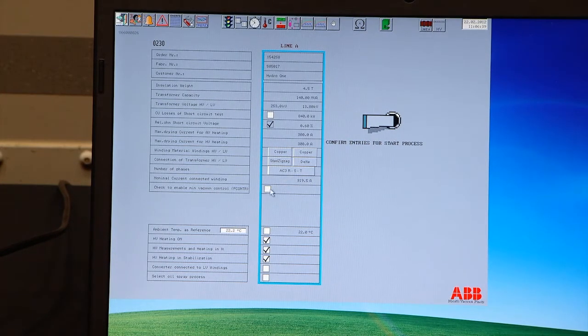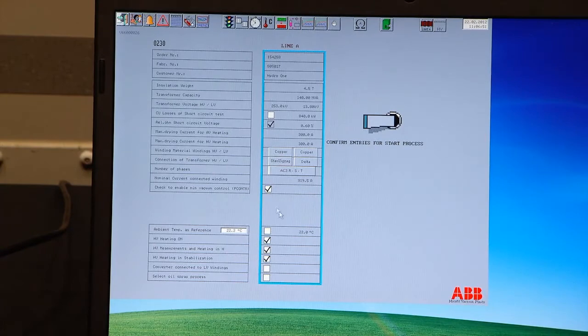Now come another few options. You can limit the vacuum in the transformer if the transformer tank does not take full vacuum. Then you check this box, and you have a parameter for that. That means that you can go down maybe to 500 millibar, maybe 700 millibar or something. Where do you set that? That comes as a parameter on this page here later. Okay.